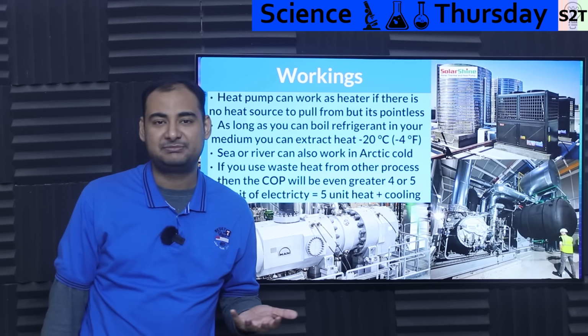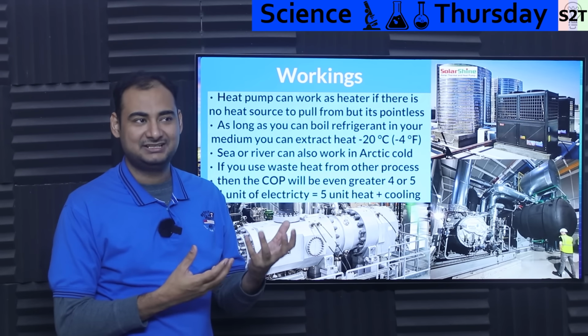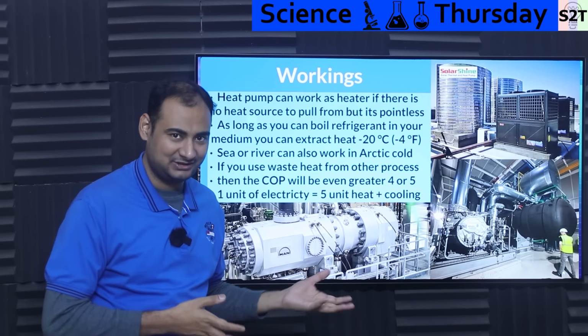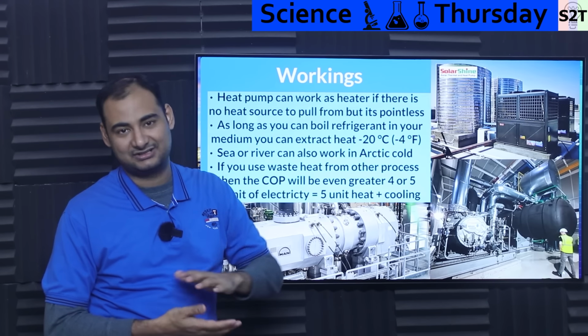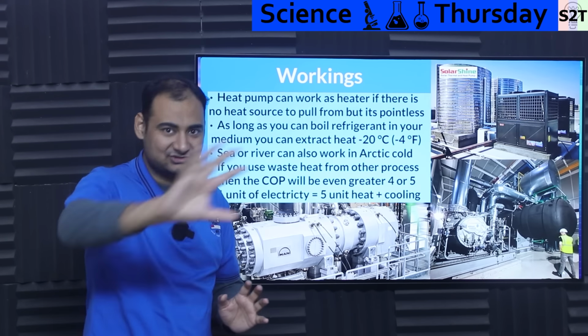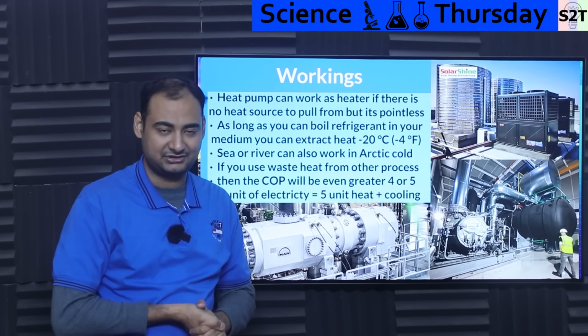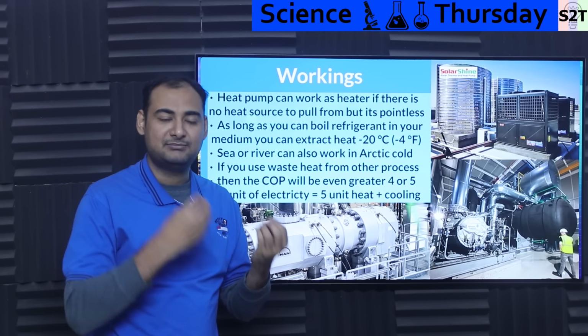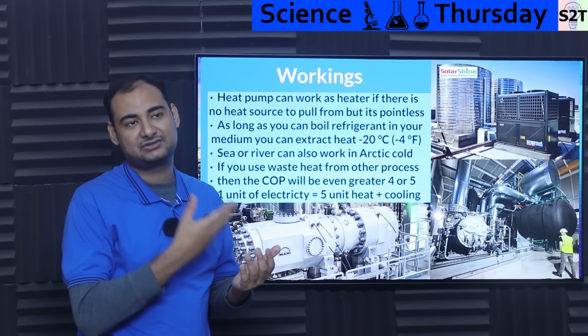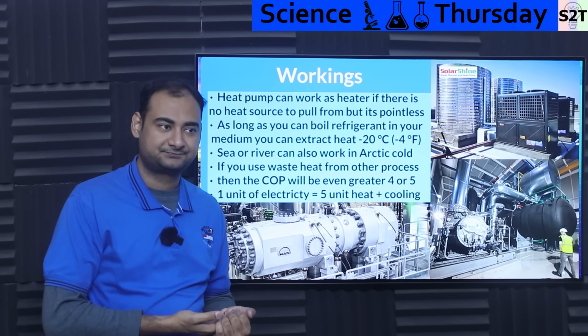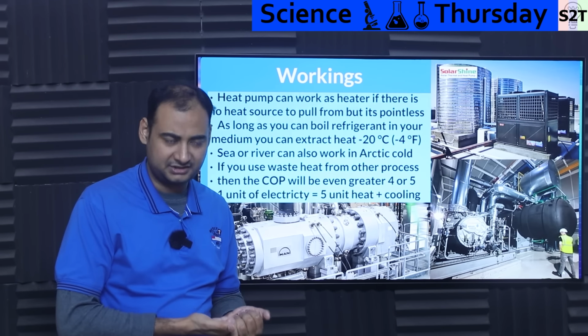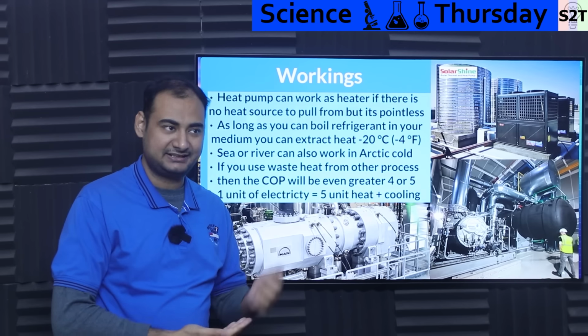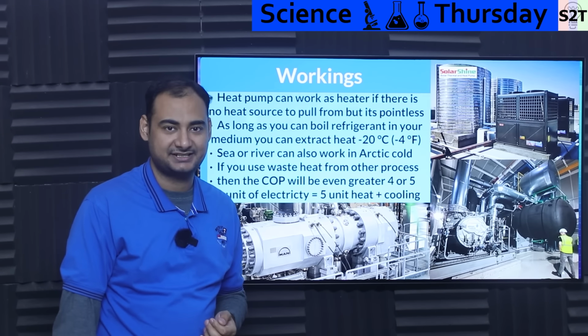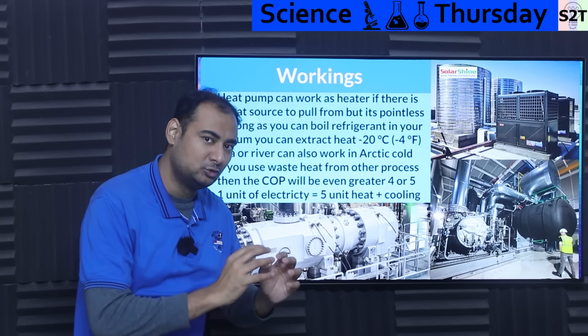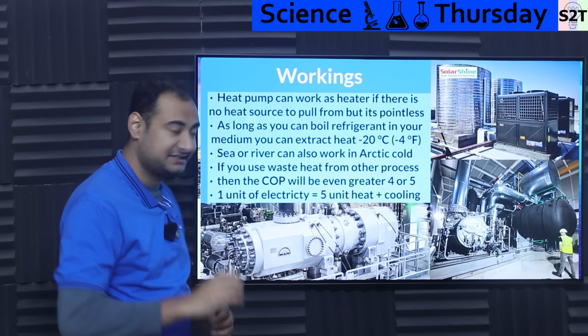A lot of people have figured out that once we boil something, generally there's a stage where we have to cool it down, or you have an exhaust that's already cooled down. So what if you take that exhaust heat and dump it back into the circulation? Even with a gas boiler, imagine the feedstock, instead of coming in at 30 degrees Celsius ambient water, comes in at 80 degrees Celsius, and it only has to target 120 degrees Celsius. It's much less fuel consumption. So that's the whole point.